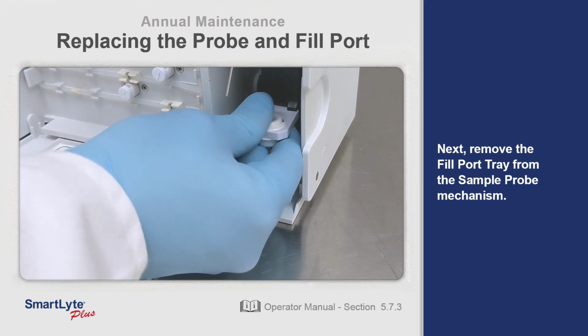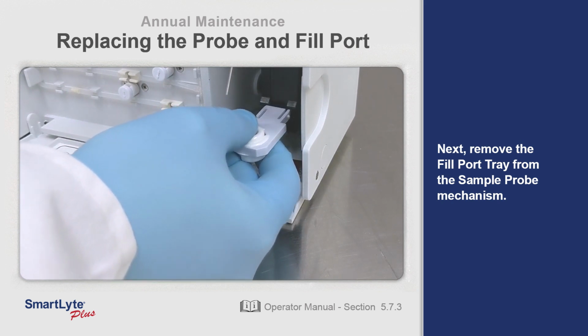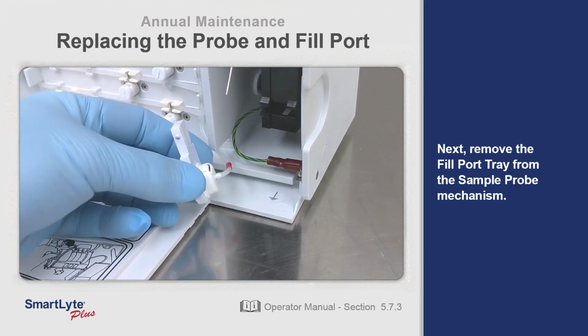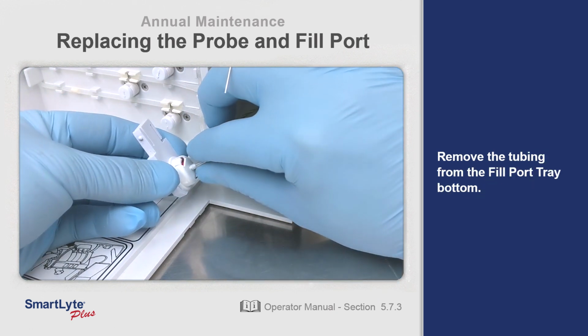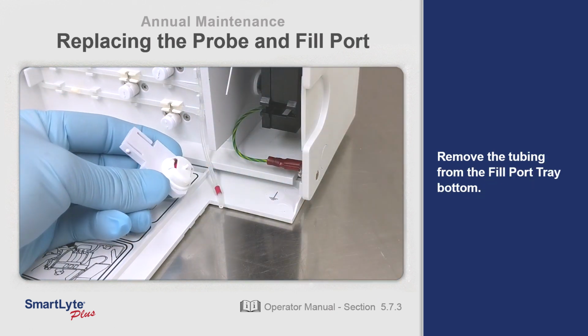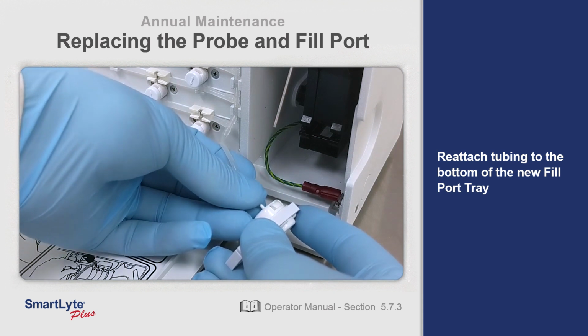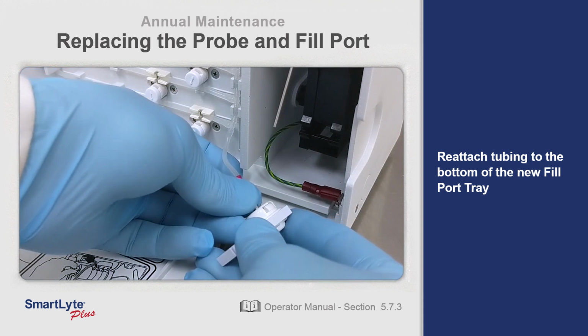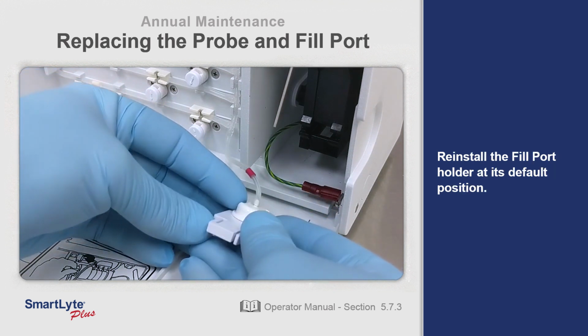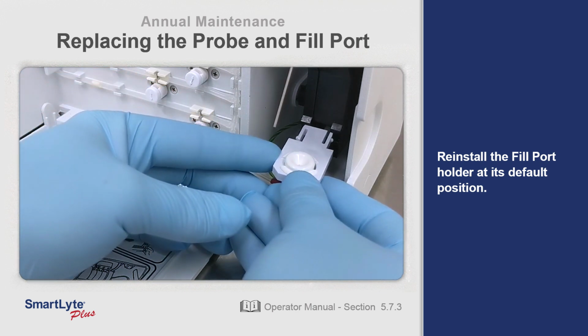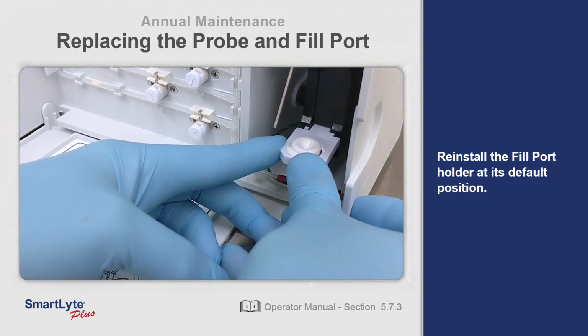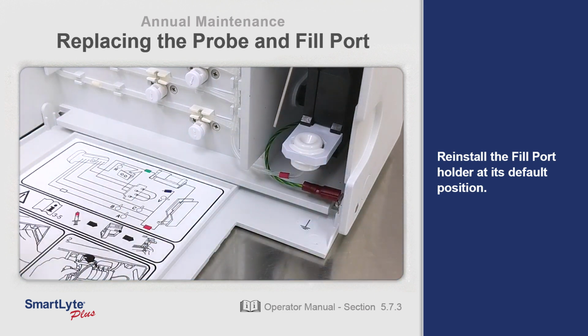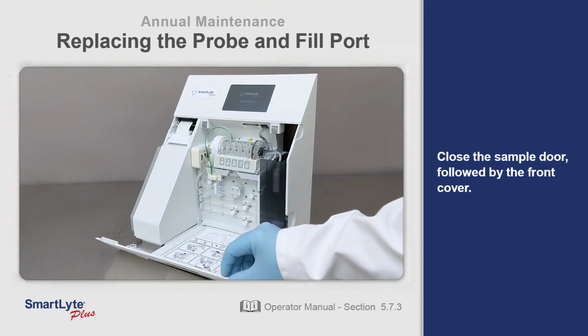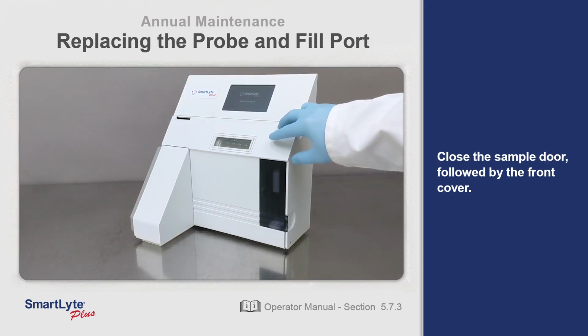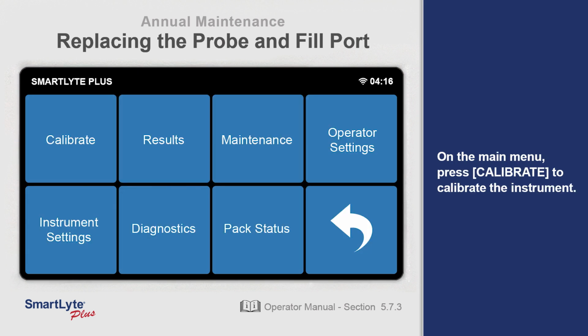Next, remove the fill port tray from the sample probe mechanism. Remove the tubing from the fill port tray bottom. Reattach the tubing to the bottom of the new fill port tray. Then, reinstall the fill port holder at its default position. Close the sample door followed by the front cover. On the main menu, press Calibrate to calibrate the instrument.